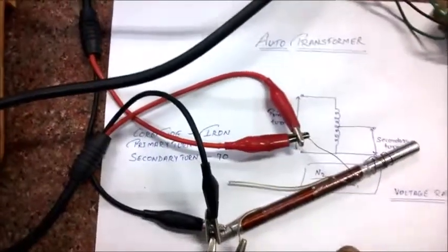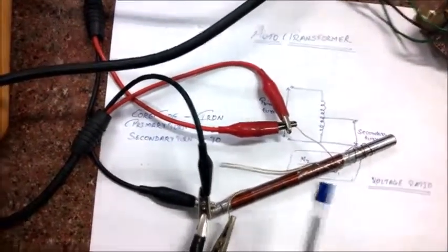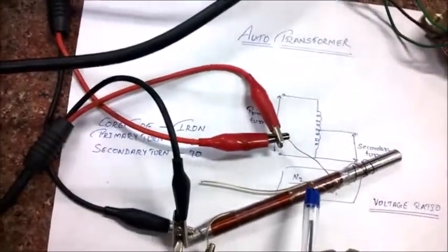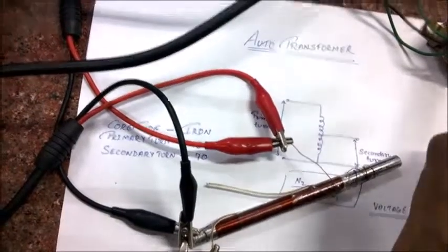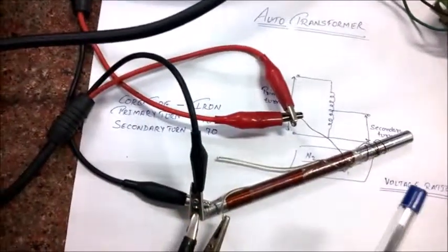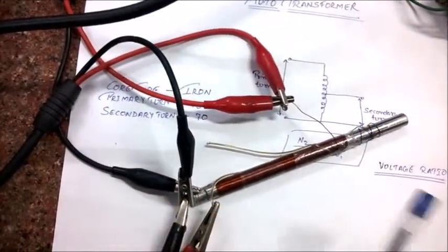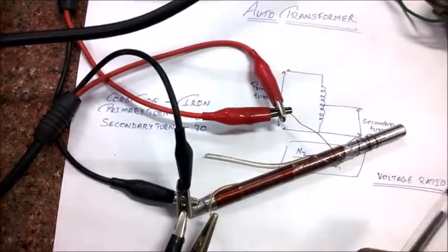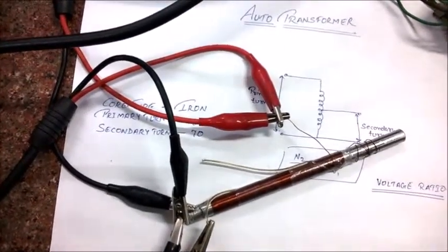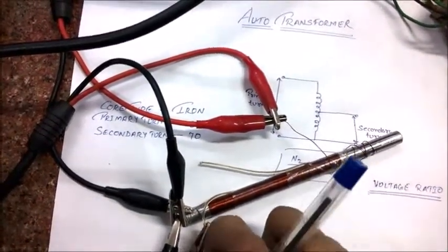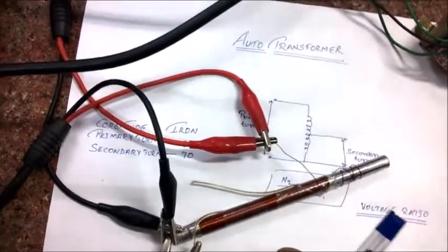Now I would like to tell you what the applications of auto transformers are, I mean unique applications which are done only by this transformer and not a two winding transformer. The two major applications are boosting of supply voltage by a small amount in distribution systems to compensate voltage drop, and auto transformers with a number of tappings are also used for starting induction motors and synchronous motors.